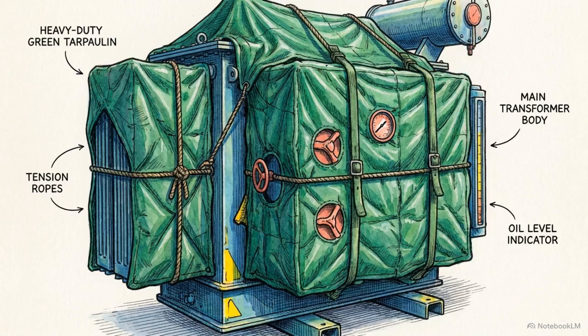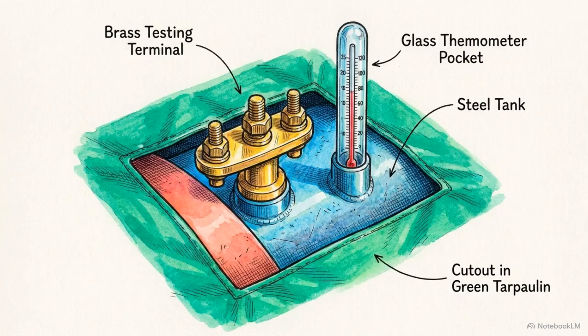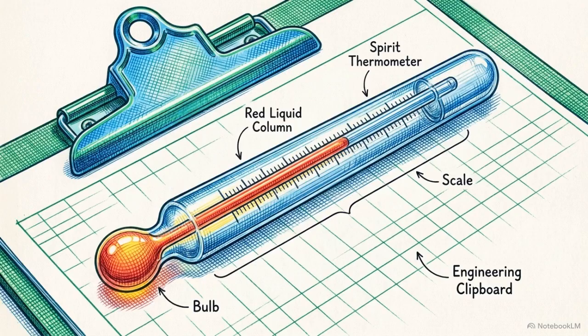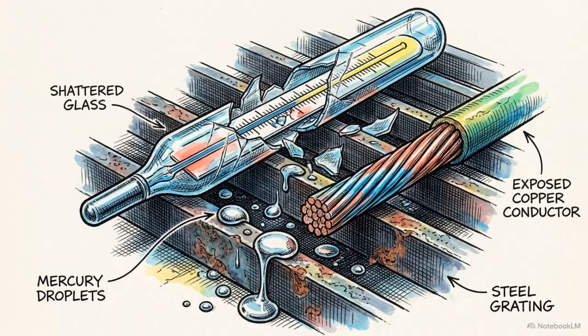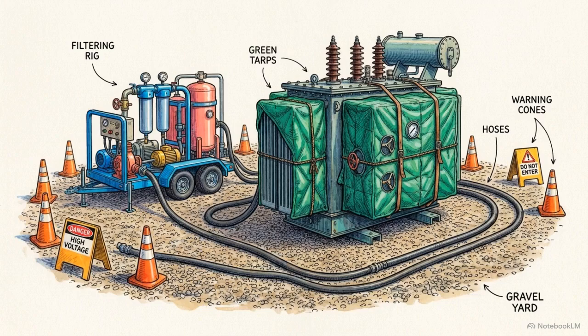Wrap the main tank in tarpaulins to trap heat, but leave all test terminals and thermometer pockets exposed for monitoring. Use only spirit-type thermometers in the pockets. Mercury thermometers are banned, as a single break will chemically and electrically ruin the core. These setup steps act as physical safeguards against pressure and contamination before the circulation begins.